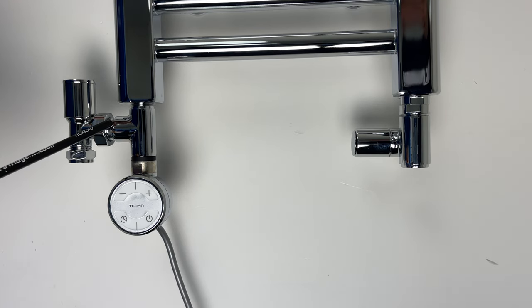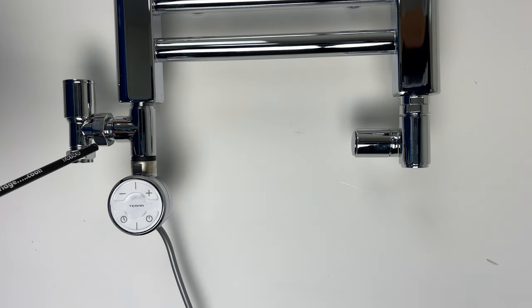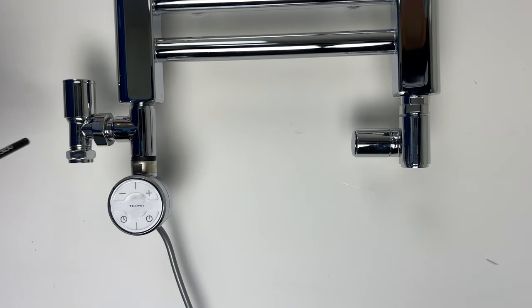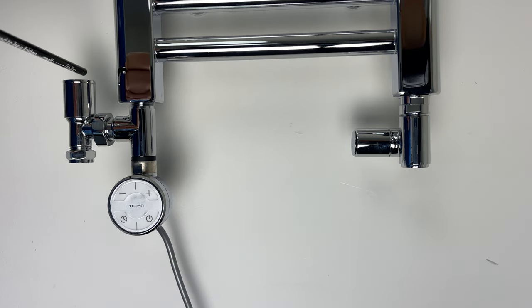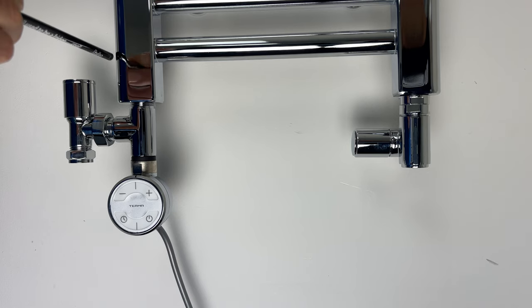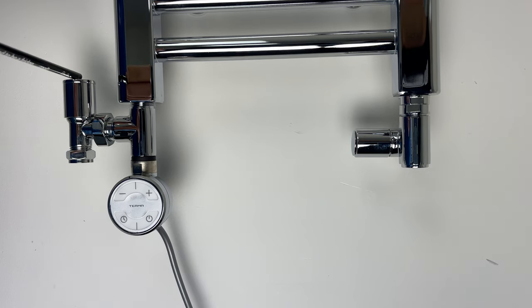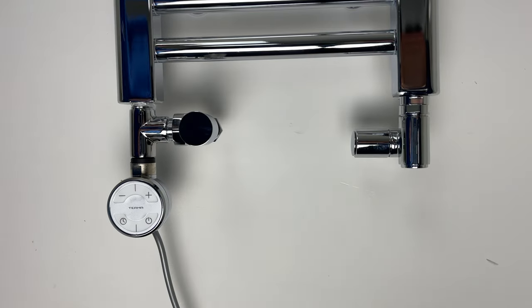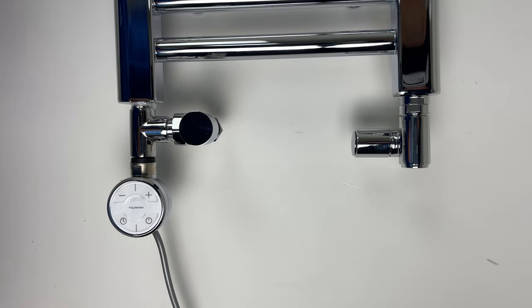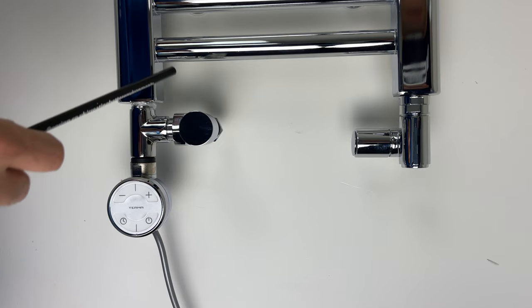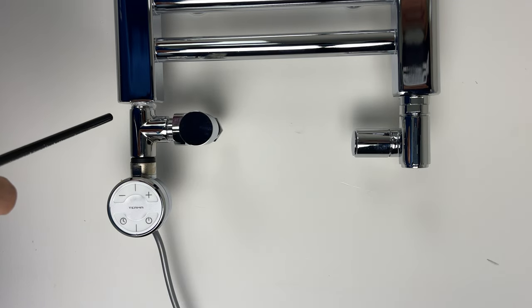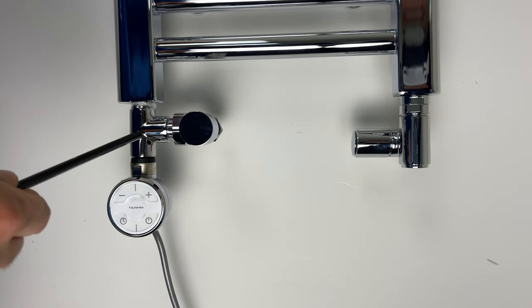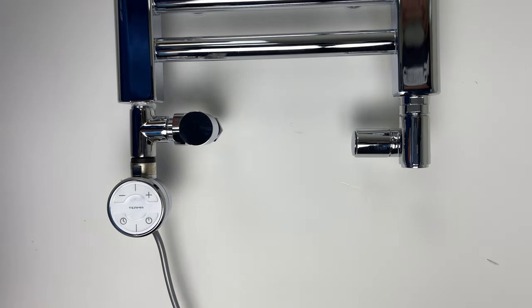T-piece option will add or take away from your pipe center. As you can see here, it is actually gone wider than the towel rail, so your pipe center is approximately 65 millimeter extended. If we can't extend our pipe center, we can install the valve underneath the radiator, which will reduce our pipe center 65-70 millimeter on this way.